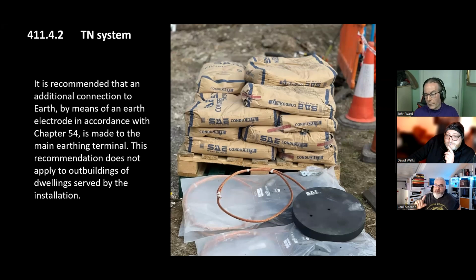So one other thing, and this is controversy now. I don't want it to be deliberate controversy, but I'm going to say it. This is a precursor to mandatory earth electrodes for every installation. We know they do it around the world. It's coming. Now, everyone can argue it's a good thing because it lowers your local impedance. However, what this does as a side effect is it masks a high resistance PEN joint, because what you're doing is giving a low impedance earth electrode reference for network currents to flow down and into.